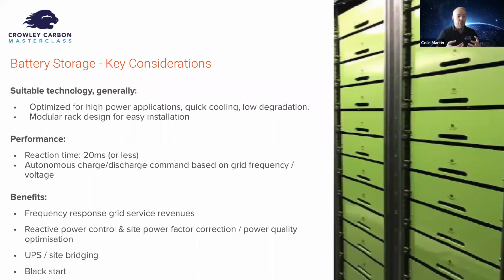Some of the benefits we're touching on, and we'll come on to these later in the presentation, is the grid services that are available from these particularly fast acting products. A battery can pretty much react instantaneously to any frequency variations it observes on the grid, and it can act then to stabilize the supply into the plant and also into the grid nearby. And those can be very lucrative from a revenue point of view. So again, stepping back and coming into a holistic solution where you are decarbonizing, but yet still maximizing your commercial returns to give an overall good return for a decarbonisation project. The batteries are an essential building block of that whole approach.